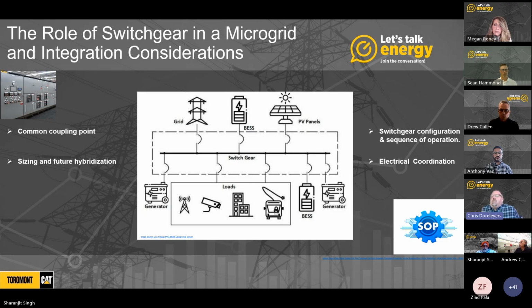Sure. So as we were talking about earlier, the switchgear is electrically at the center of the system, and the controls are like the conductor or the traffic cop—they help institute when breakers should operate and when loads and sources should be connected. This is why it's so critical that when we're thinking about integration, these two items are done, or looked at, at the same time.